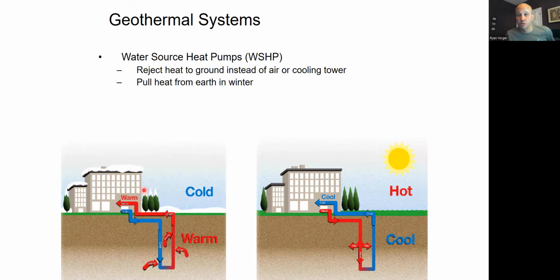When you do this, the geothermal heat pumps for these zones, some can be running heat, some can be running cooling at the exact same time, just like the other water source units did, right? Some are dumping heat, some are taking it out. But on an annual basis, if I put as much heat into the ground as I take out, that would be awesome. It'd be the perfect storm scenario, and I would not need any other heating and cooling sources. I would just have these geo units dump heat to the ground and take heat out of the ground, right?